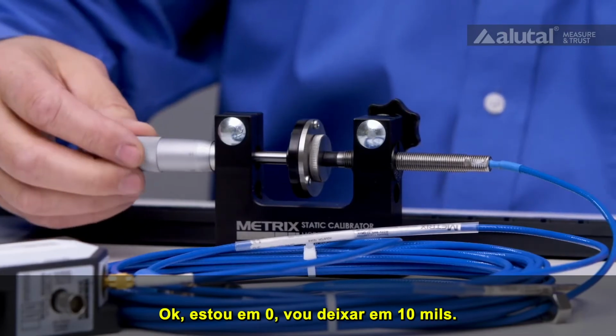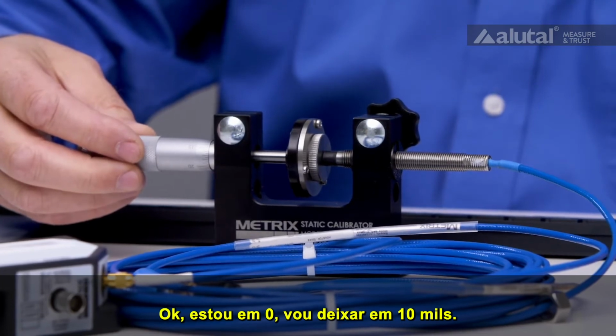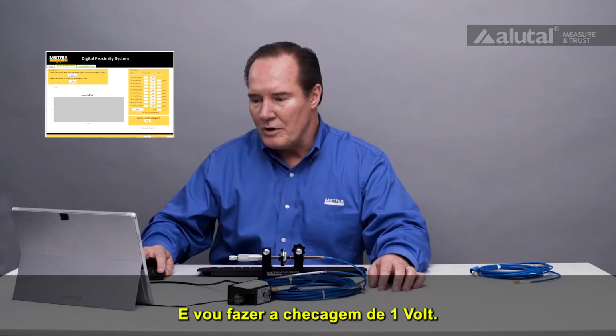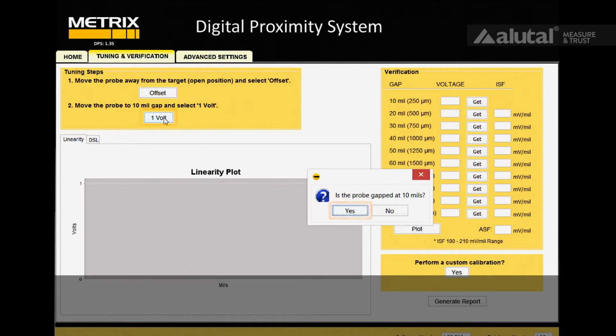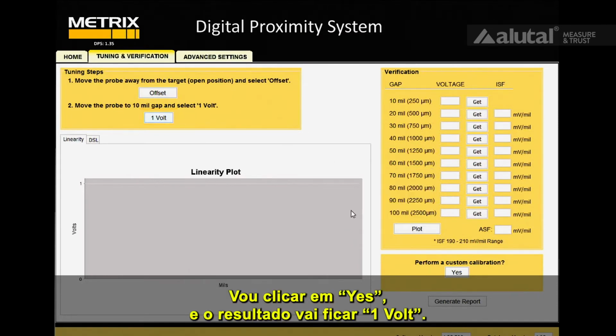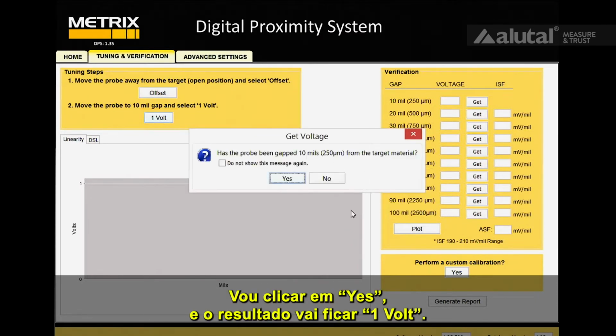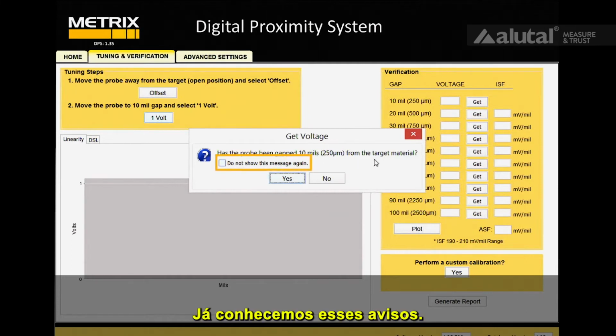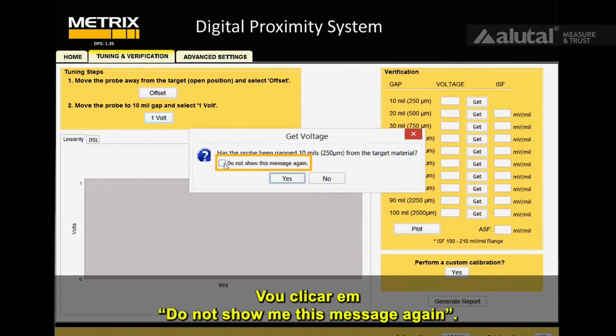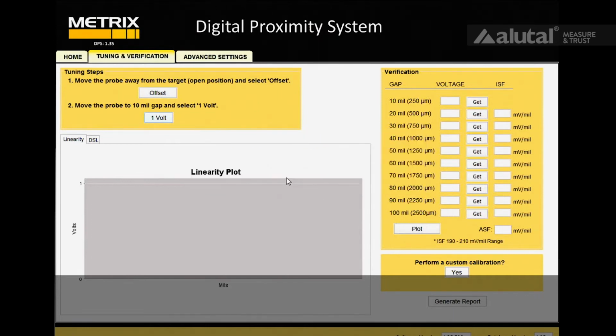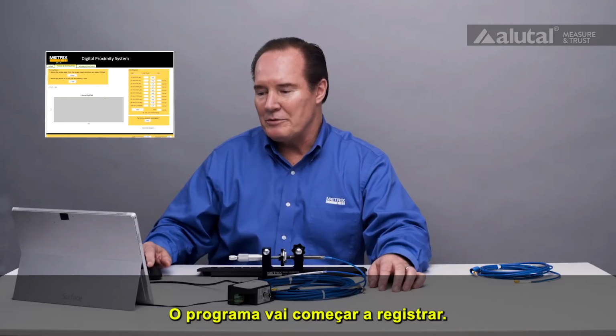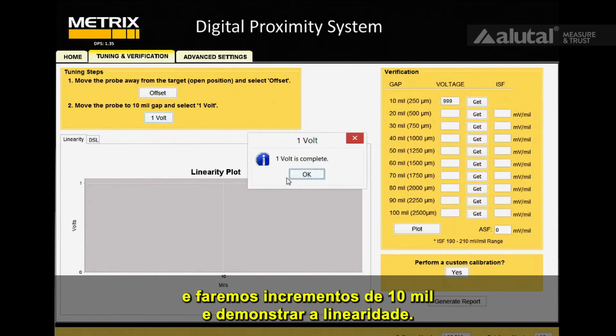Okay, so I'm at 0. I'm going to go ahead and go to 10 mils, and then I'll do the 1-volt check. I'll say yes, and then output will become 1 volt. Okay, we know we get these warnings. I'm going to go ahead and say, do not show me the message again. And it will fill in, and we should start close to 1, and then we'll do 10 mil increments and demonstrate linearity.